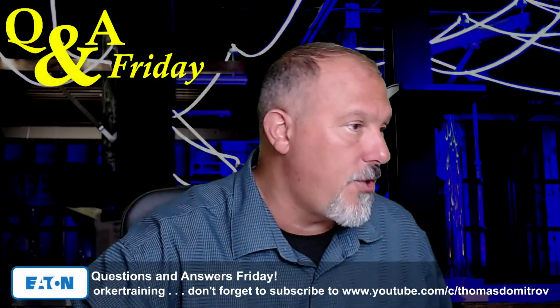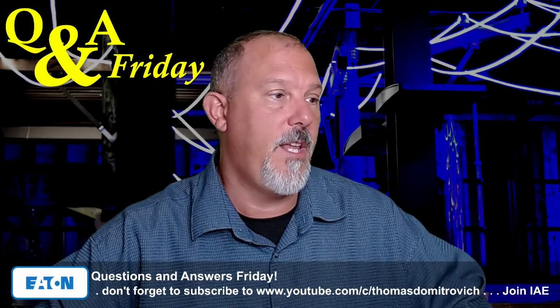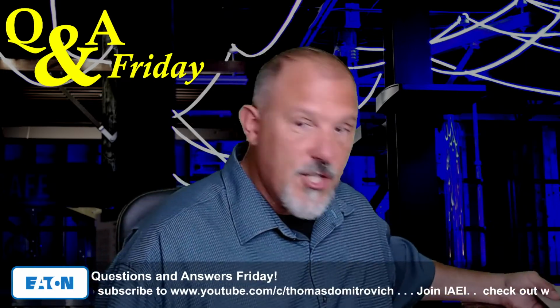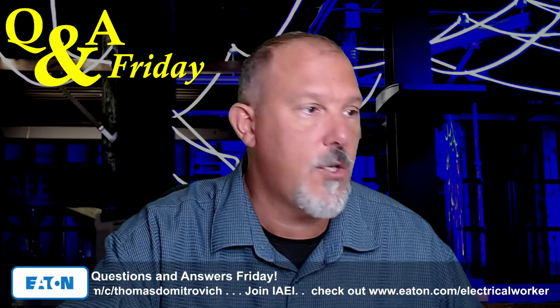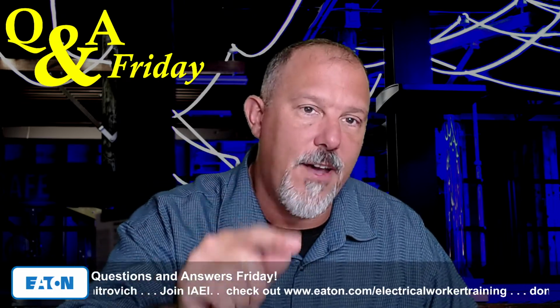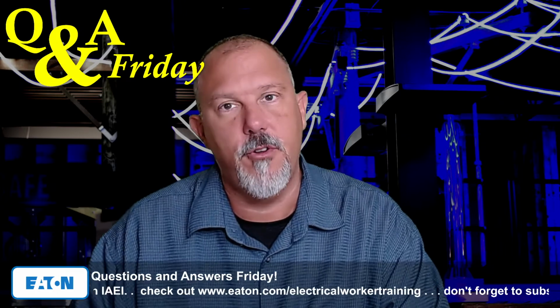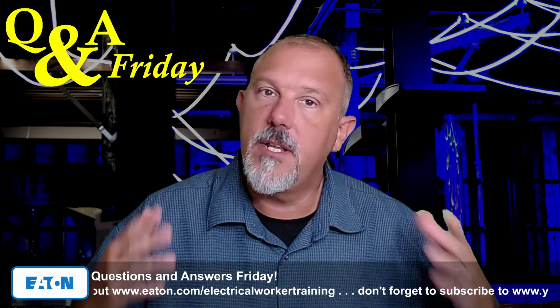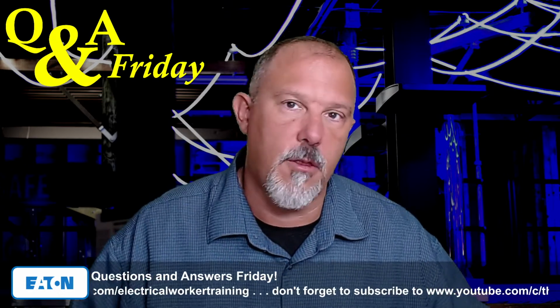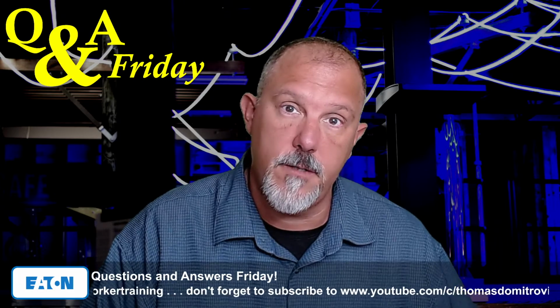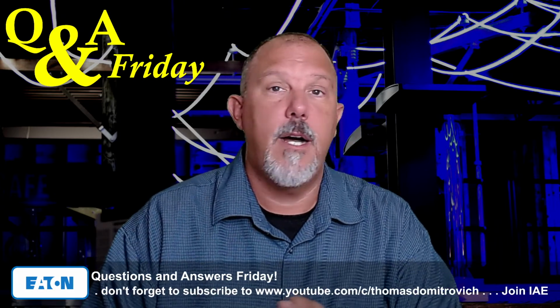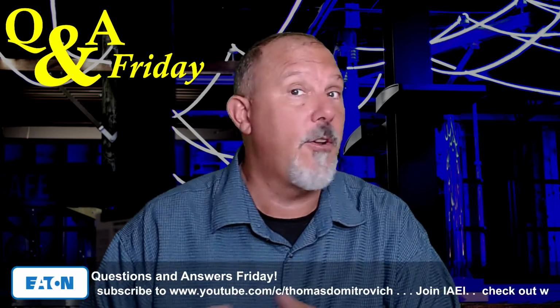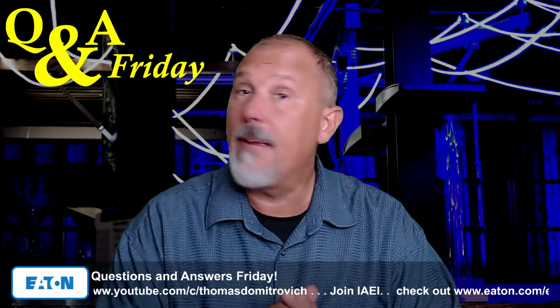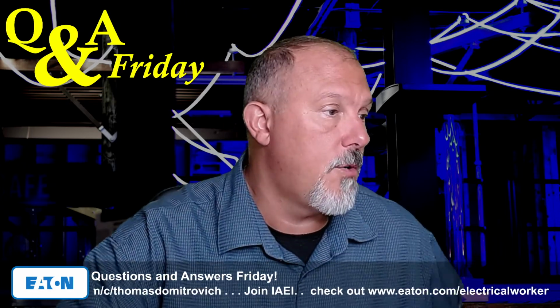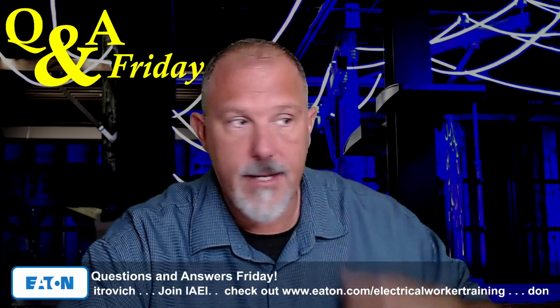And so my answer to you, Navneet, is yes. If it's less than that instantaneous, then you are selectively coordinated, or you're coordinated for that value of current. If it's not the three-phase bolted fault current value, you can't say I selectively coordinate, because that means all currents, all times, and all the ways up to the three-phase bolted fault current. If you pick another value of current, then you're accepting some risk with regard to whether or not the current will be greater than whatever you pick, right? And that might be perfectly fine for your application. So hopefully that helps you, Navneet Garg, in answering your question.